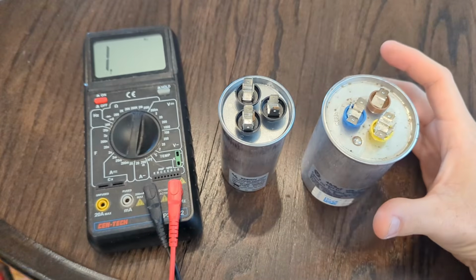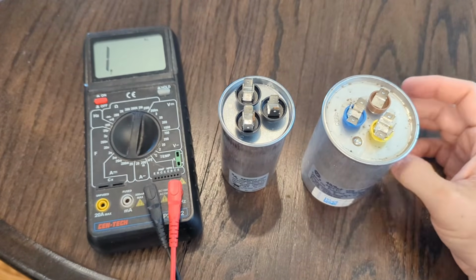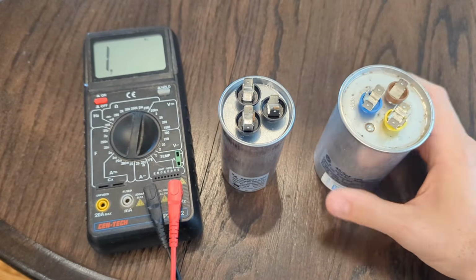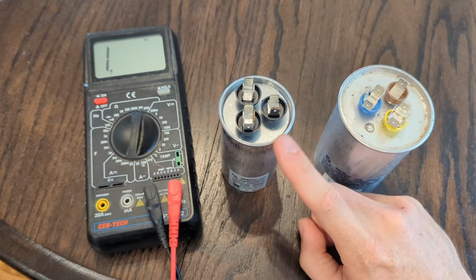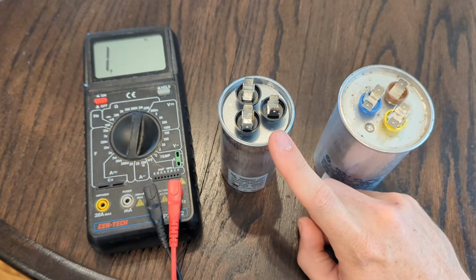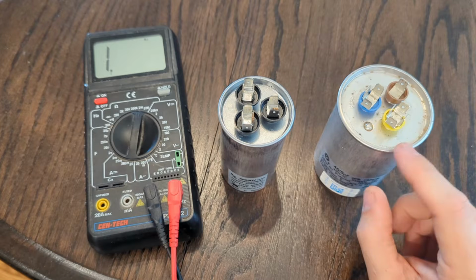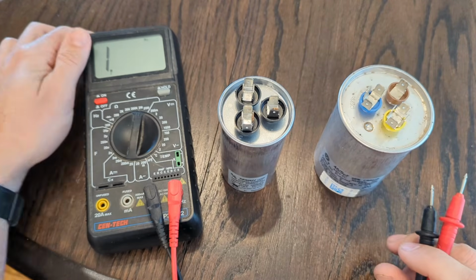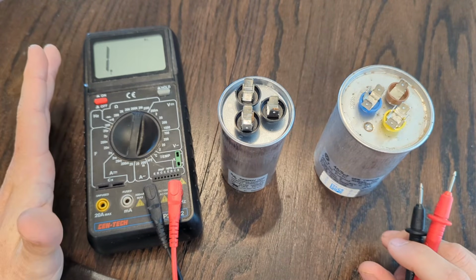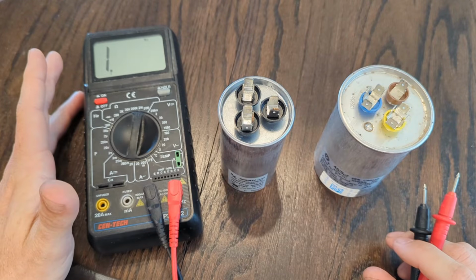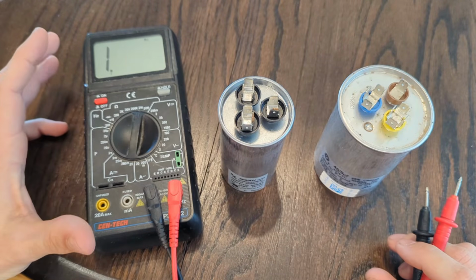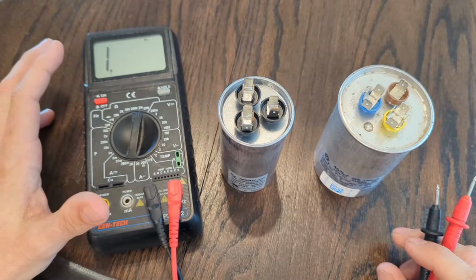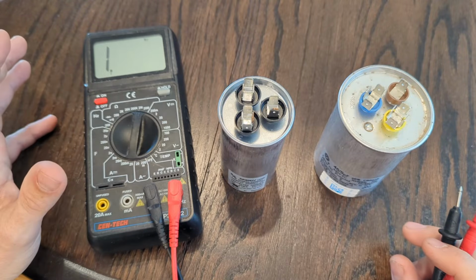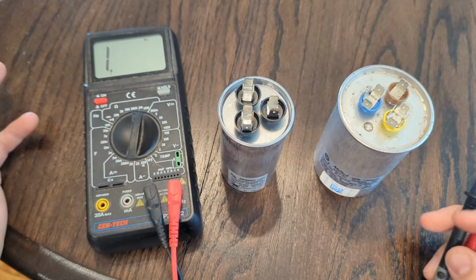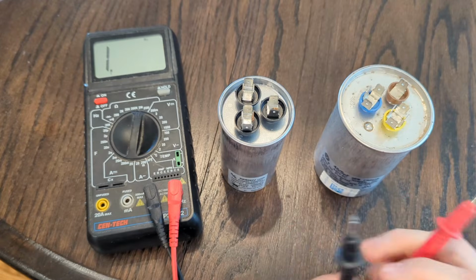Okay, we're going to do a quick test with a multimeter to make sure that this capacitor is bad. I've got one that I know is good here. So I'm going to show you what a good one will look like and then why this one isn't working. So this is a standard multimeter. This is not one that has a specific testing for capacitors, which is probably more common than not. So this is going to be a simple test. If you have one that's got a capacitor setting, obviously use that. It can give you more specific data.